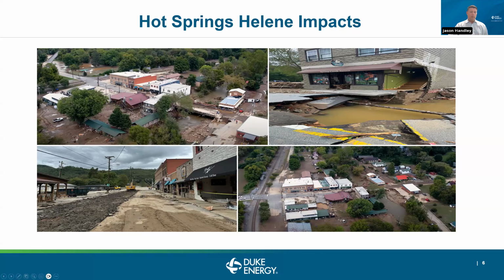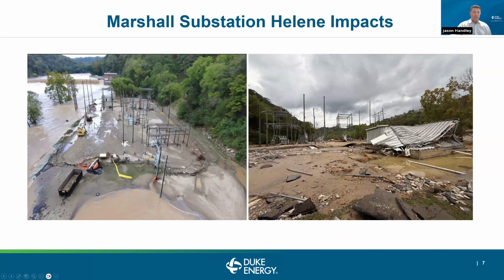It also had a significant impact on our substation that feeds the town. Besides the French Broad River, the Marshall substation was basically flattened by Helene. The picture on the left shows some pieces of major equipment that are still there, but a lot of pieces were damaged or missing. The substation transformer was knocked off its pad a little bit askew, and our controls area, where all of our relaying and protection and everything is, was completely washed away. There was nothing left inside except debris.